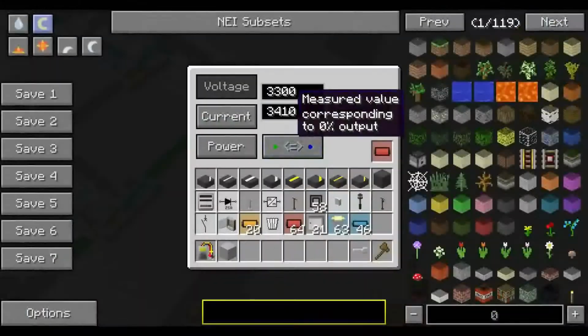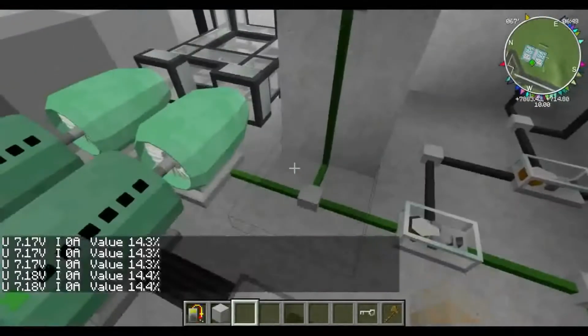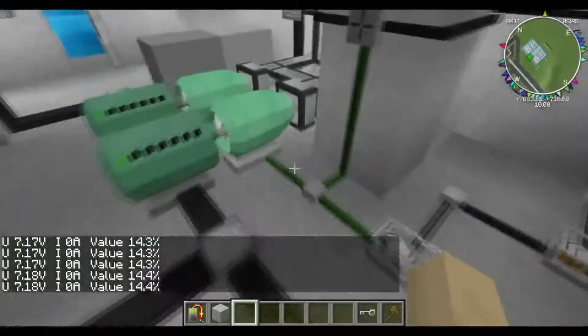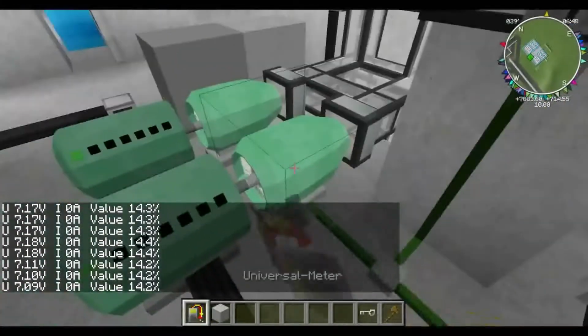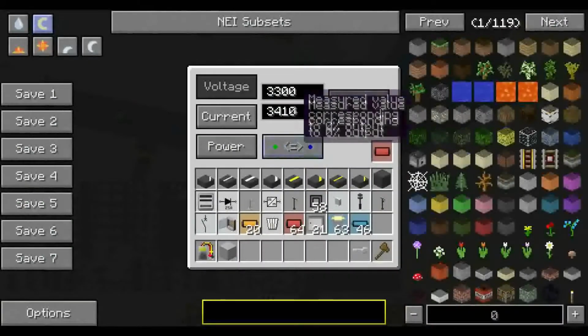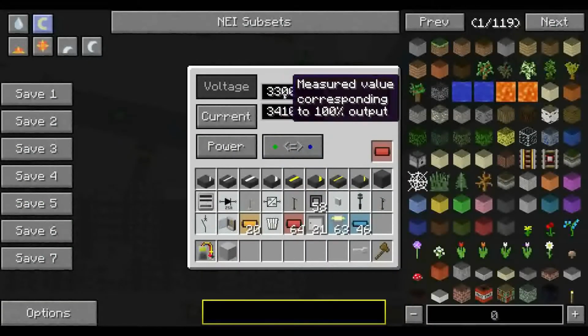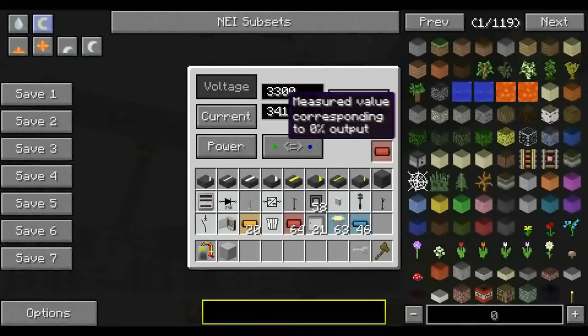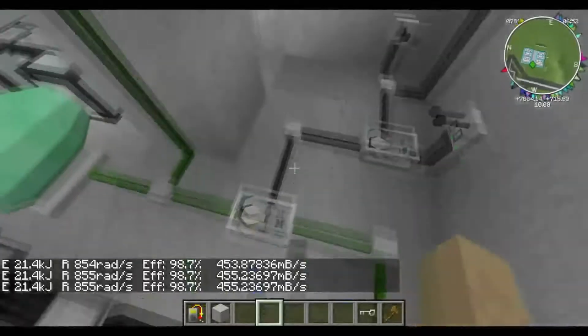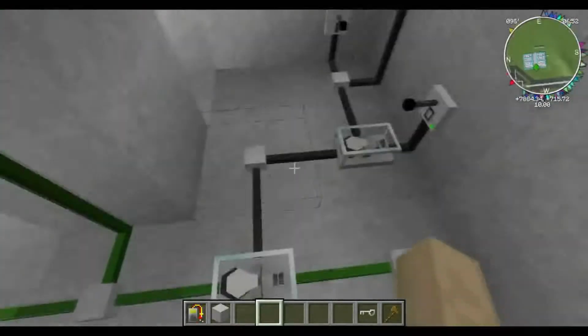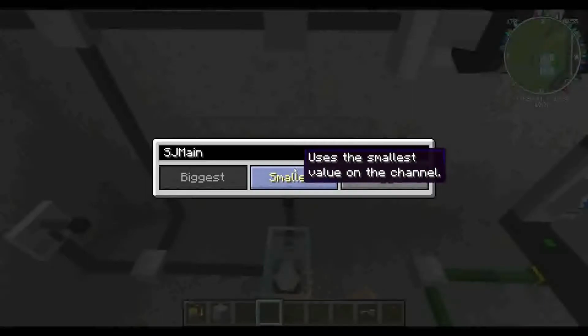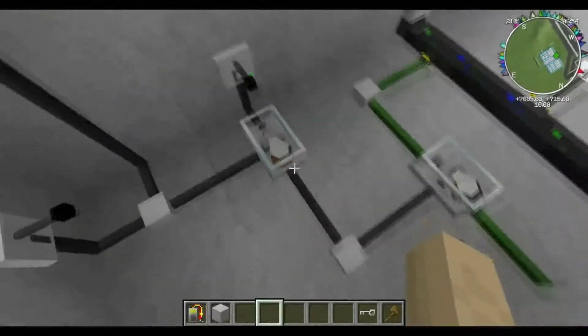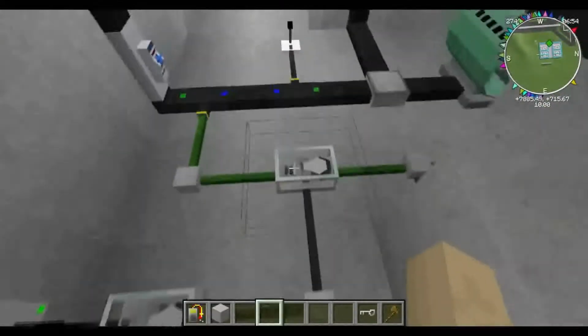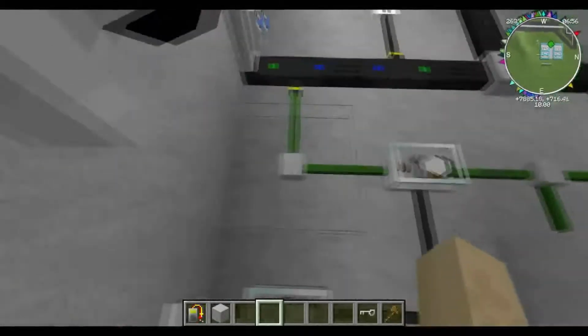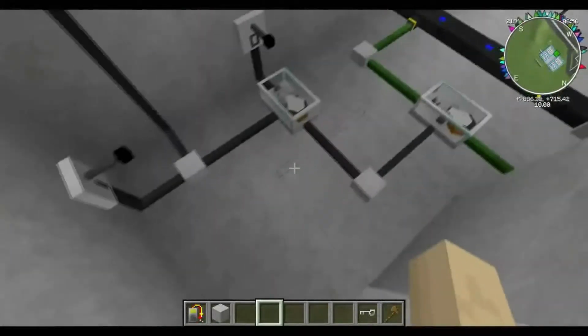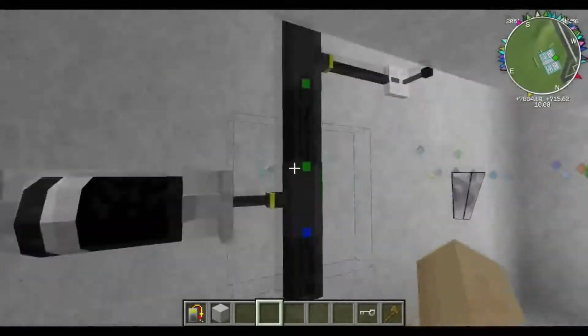So right here we have the throttle. Like I said, the throttle is like how much power, how much steam it needs to maintain that voltage. So my voltage is from 3.3 kilovolts to 3.41 kilovolts, and this relay here is where the system comes in. So this is the main switch, goes in this line to here, which kicks in this relay to connect this line, but the bypass switch is here.